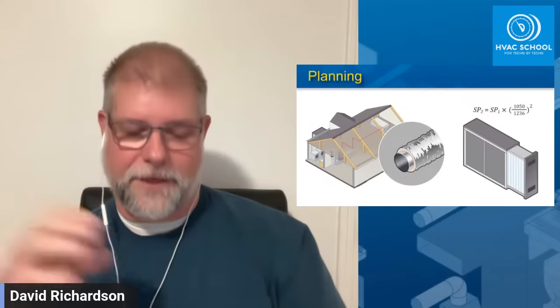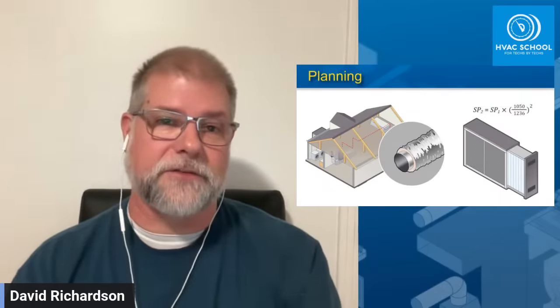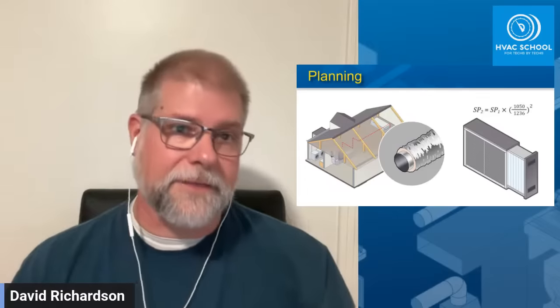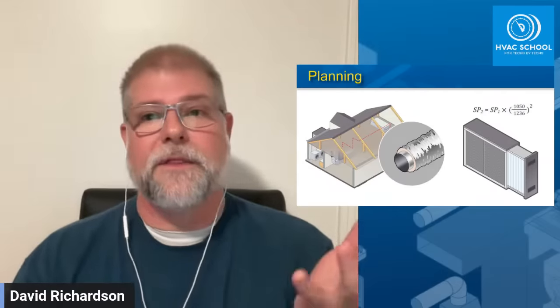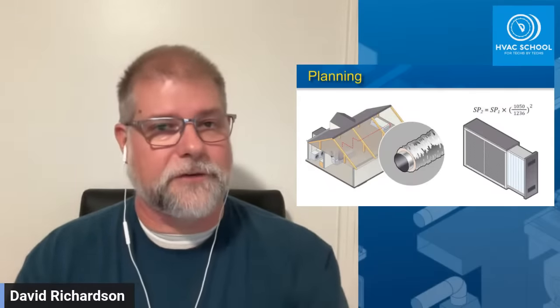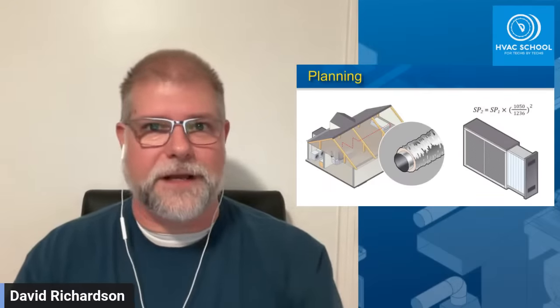Turning vanes are an easy solution if you have access — you can find single-wall vanes residentially, or fittings with a radius throat and radius heel if you have room. You'll often be limited by the constraints of what you can deal with and the customer's budget — ultimately they have to want to buy it. You have to translate technical findings into simple language: compare it to traffic analogies, vital signs — these are the things that help customers make sense of it. Tie the pain they've been having to the symptoms you're measuring and finding a problem for.